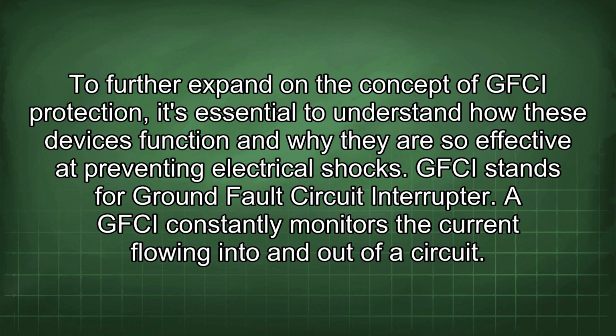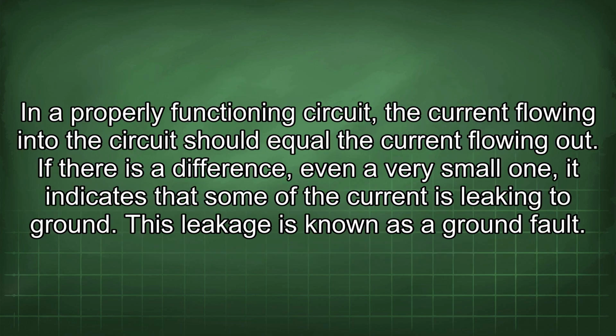To further expand on the concept of GFCI protection, it's essential to understand how these devices function and why they are so effective at preventing electrical shocks. GFCI stands for Ground Fault Circuit Interrupter. A GFCI constantly monitors the current flowing into and out of a circuit. In a properly functioning circuit, the current flowing into the circuit should equal the current flowing out. If there is a difference, even a very small one, it indicates that some of the current is leaking to ground. This leakage is known as a ground fault.